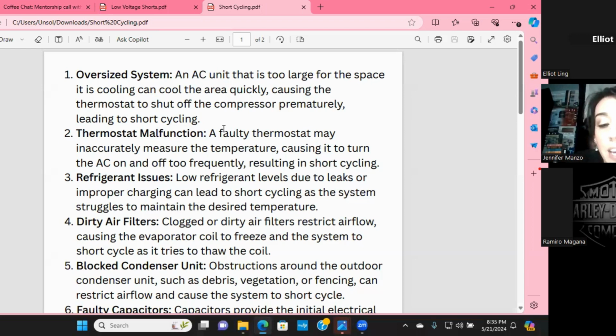So the thing that short cycling causes that does the most damage, I would say, obviously it slugs the compressor. It's not good for any component in your HVAC system, but it causes humidity. So an air conditioner, and most people don't realize this, because we know, as technicians or as we're learning to be technicians, that we are not actually providing cooling when we are fixing or installing an air conditioner. We know that we're removing heat. And that is a big thing when the unit is short cycling. If it's short cycling, it's not running long enough to remove that heat. And when we don't remove the heat, or we drop the temperature too quickly without dehumidifying.